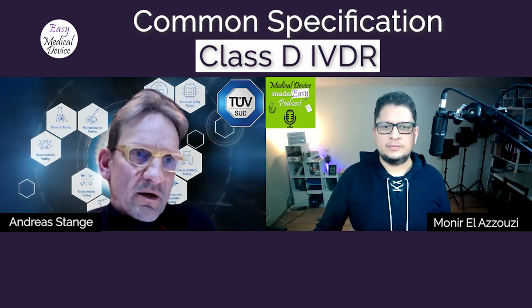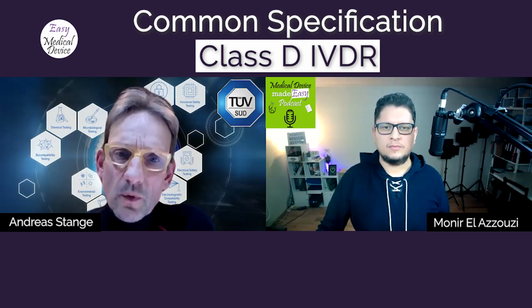Yeah, so the concept of common specification is not a new one. We have basically the same concept already under the IVDD, where these are called common technical specifications. In Article 9 of the IVDR, it is described that when harmonized standards are not good enough or not stringent enough for compliance, the Commission may adopt common specifications, which are basically mandatory for manufacturers to meet.